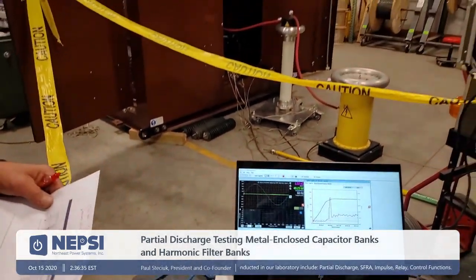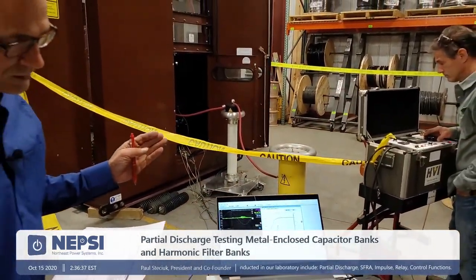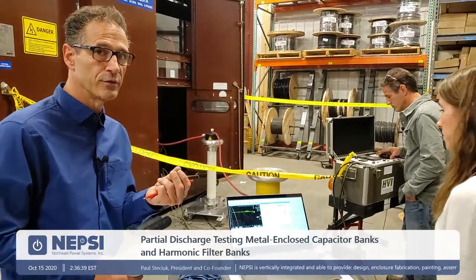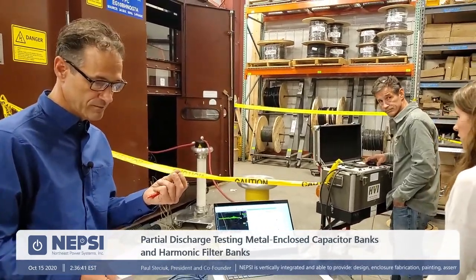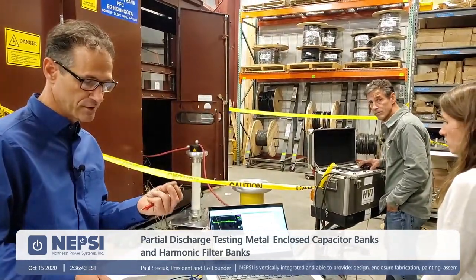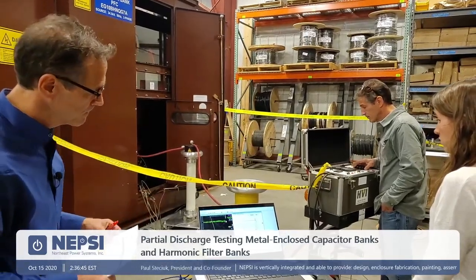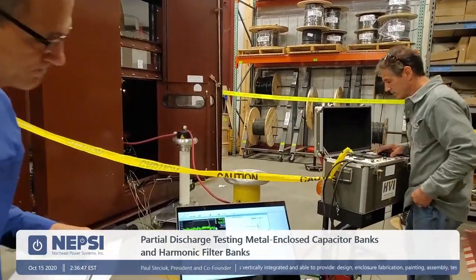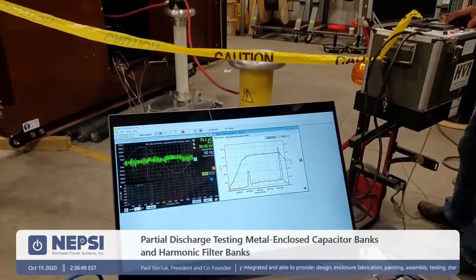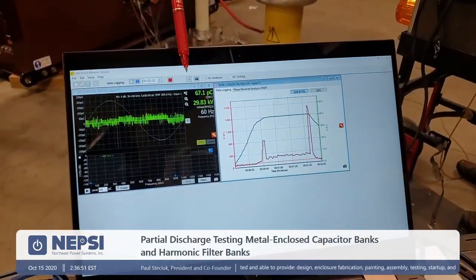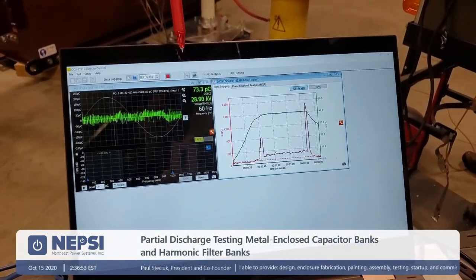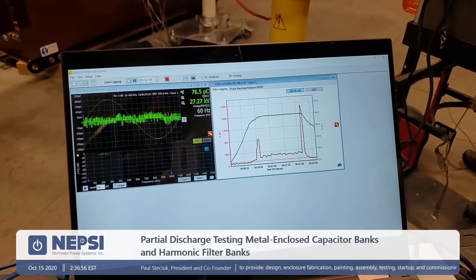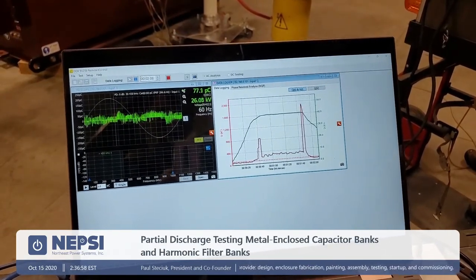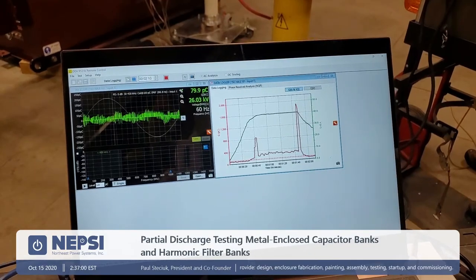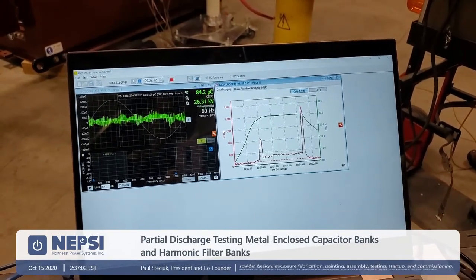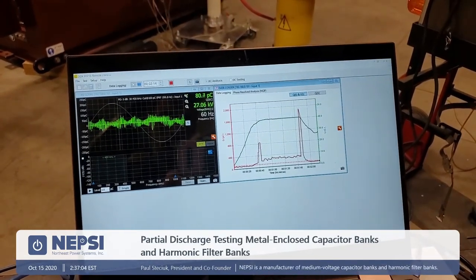Right. So we bring it down to 26.5 kV. Within 2 minutes, we have to see if the discharge rate is less than 100 picocoulombs. So I'm bringing the voltage down here. And we've already technically passed, and we haven't even gotten there. You're at 30. So 26.5. 27. Stop. Right. You're at 26. You can bump it up just a little if you want to. So Pete will make sure he looks to get that at 26.5 kV.